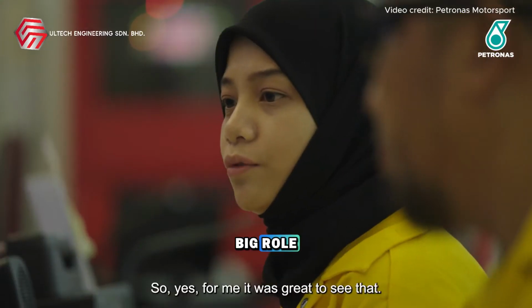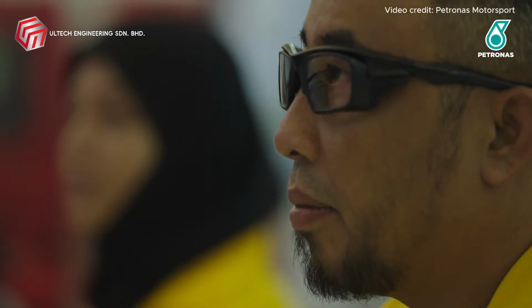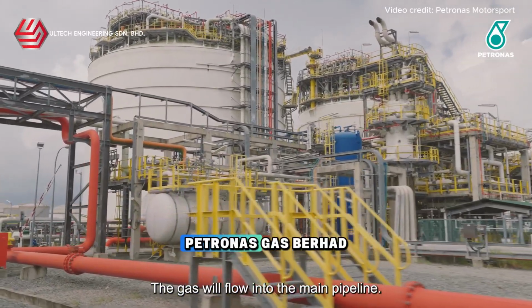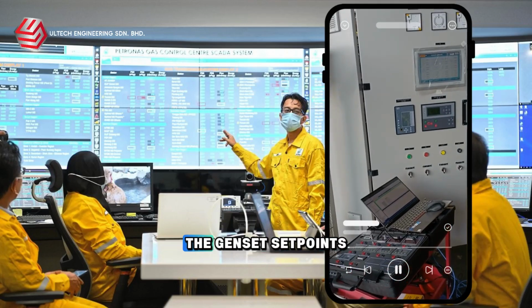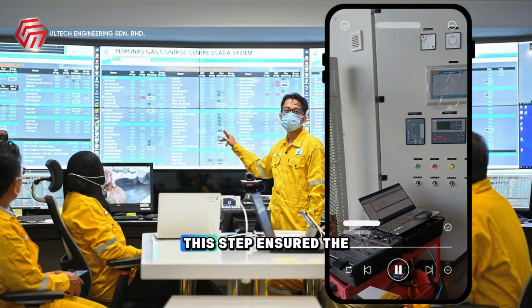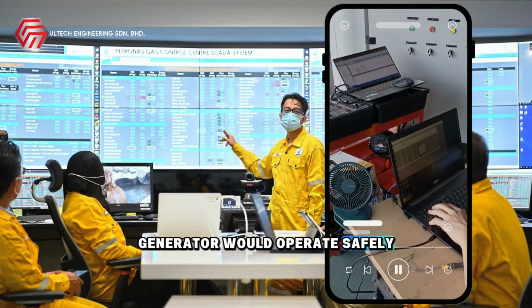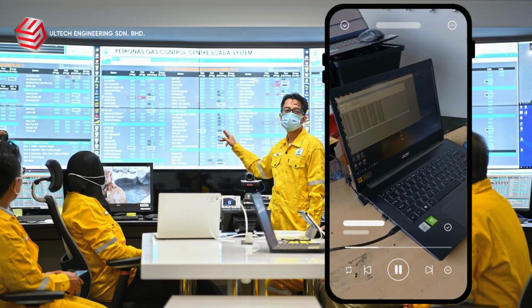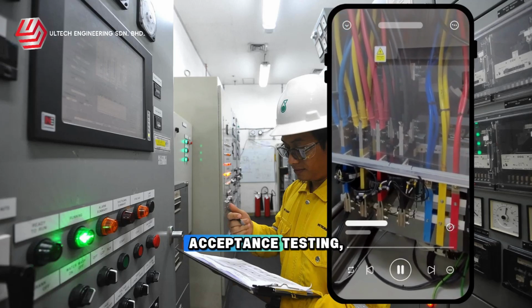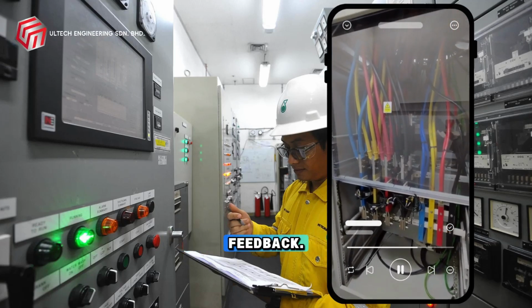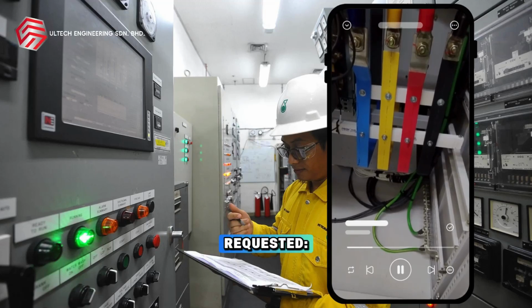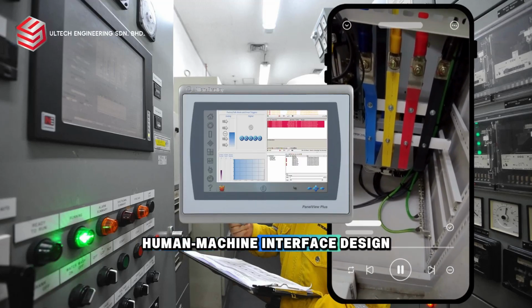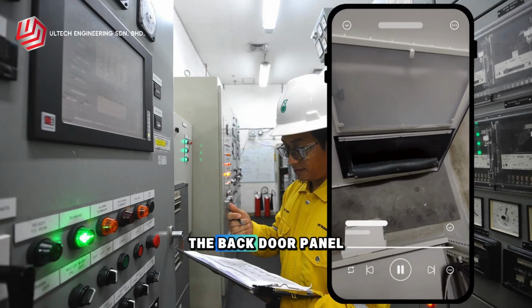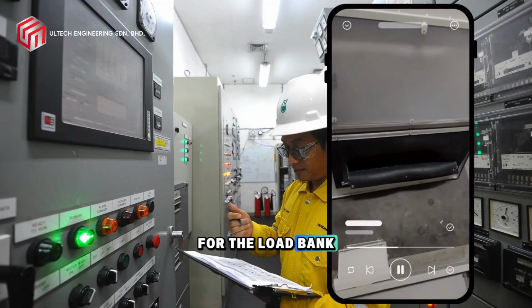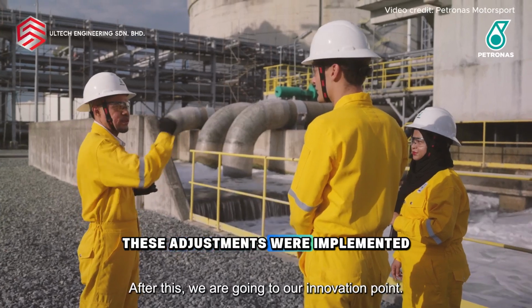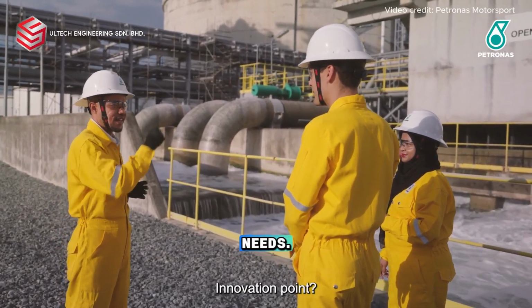Client feedback played a big role throughout the process. During factory acceptance testing, PETRONAS Gas Berhad focused on confirming all the genset set points for sensors. This step ensured the generator would operate safely and exactly as intended once installed. Then came the site acceptance testing, where the client gave a punch list of feedback. Two main changes were requested: a modification to the human-machine interface design and a redesign of the back door panel to allow better access for the load bank cable. These adjustments were implemented to fully meet client needs.